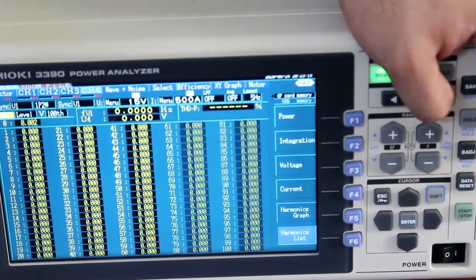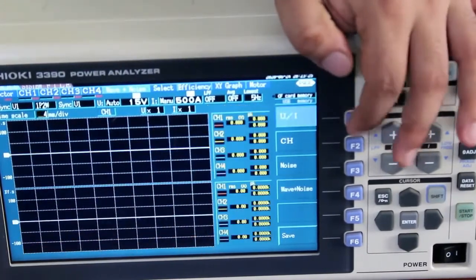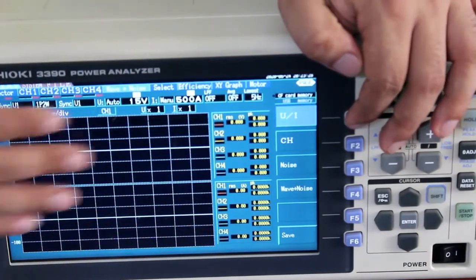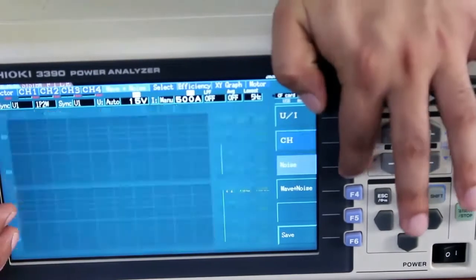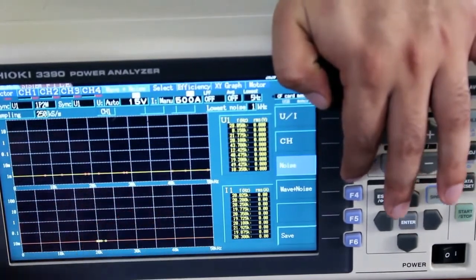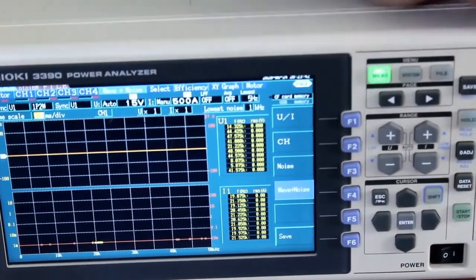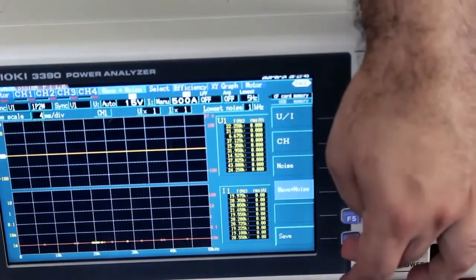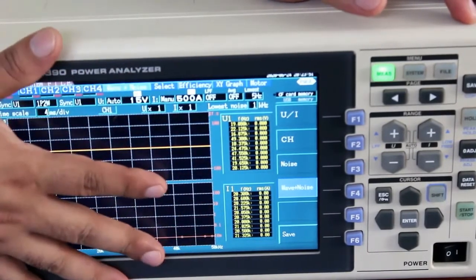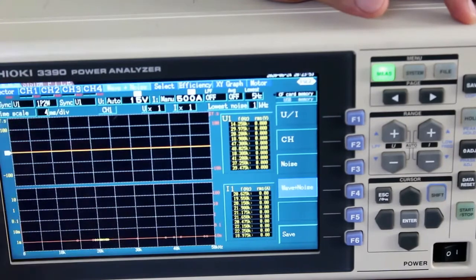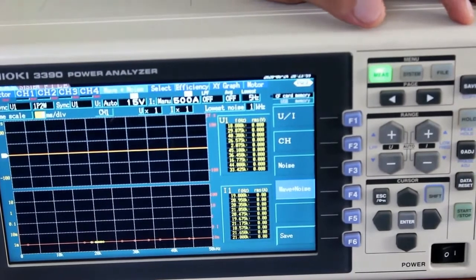Moving through the phases to channel four, there is a waveform and noise screen. Here you can see phase-wise voltage and current waveforms, and also the noise waveform. The waveform plus noise view is like an FFT analysis. There is a separate save key — pressing it saves the noise data specifically to the CF card.